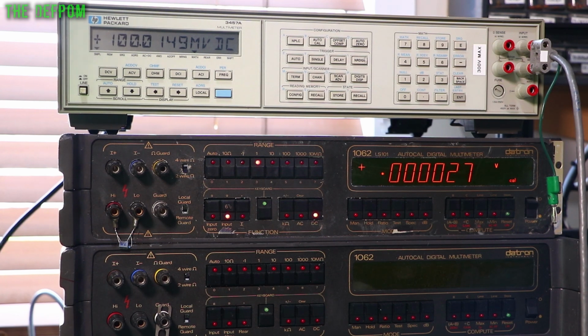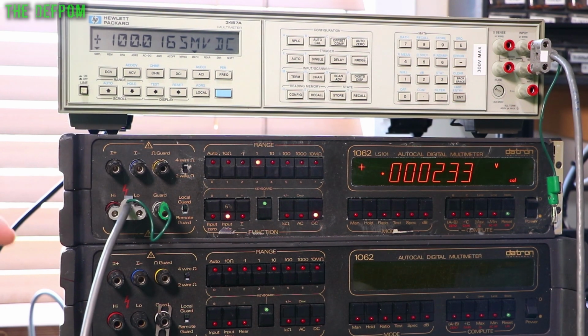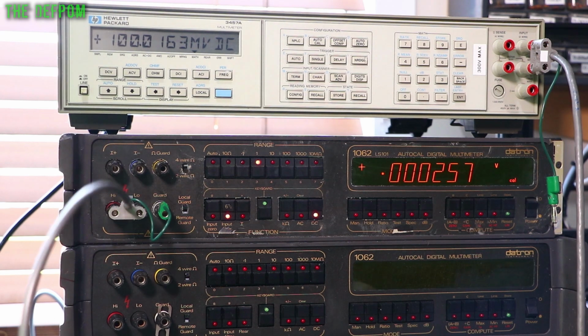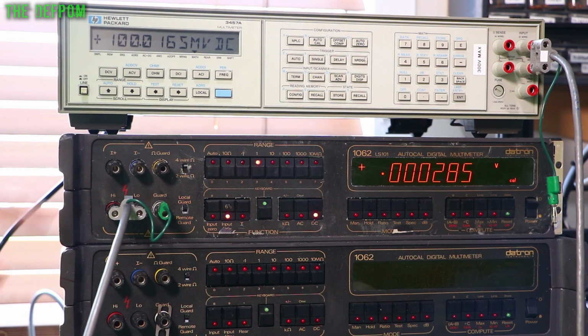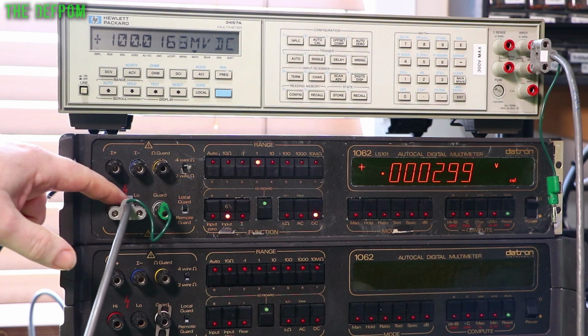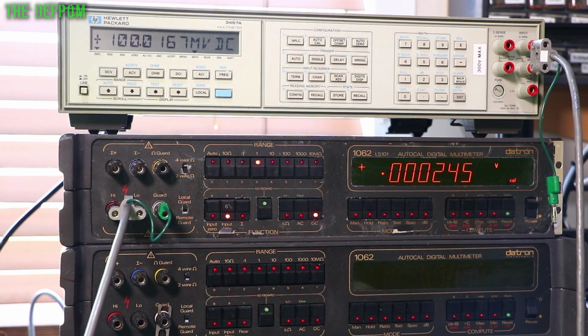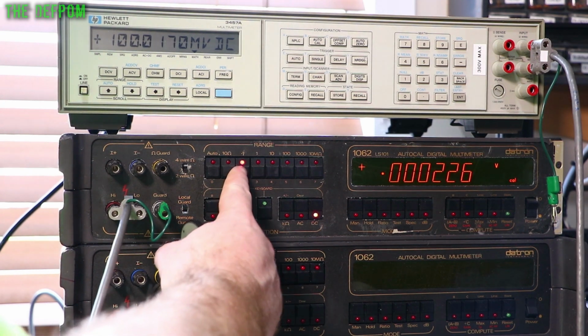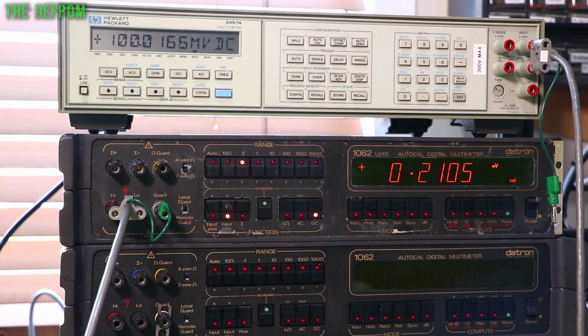There's a 10 megohm on the 0.1 volt range. Right, so that's the resistance calibrator hooked up, set to 10 megohms. I've got a little 10 nanofarad capacitor shoved across the inputs directly there, to try and keep noise down. Let's go to the 0.1 volt range and we'll see if this is quiet enough. There is a little bit of jumping around there, but it's not that bad, I suppose.